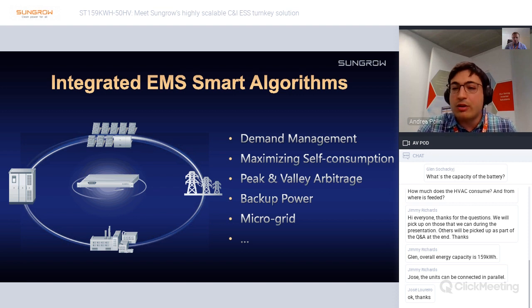The arbitrage mode allows tariffs to be entered in the local controller to establish the best times for charging and discharging the battery. In microgrid operation mode, for example, the local controller gets measurements from the battery and loads, and if the battery is low in state of charge, it will send a command to the diesel generator to start and provide grid reference, even charging the battery if necessary, ensuring standalone operation of the microgrid system.